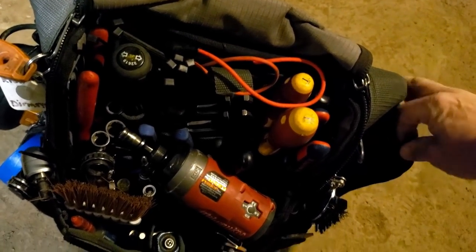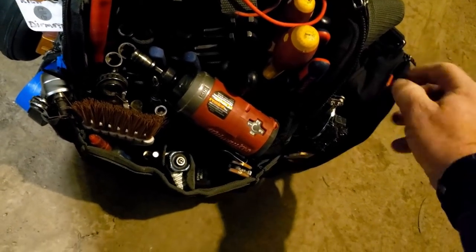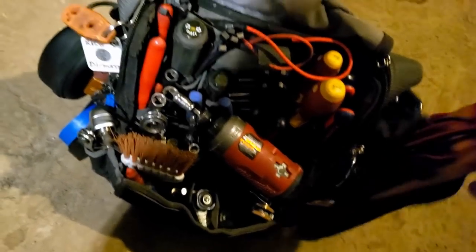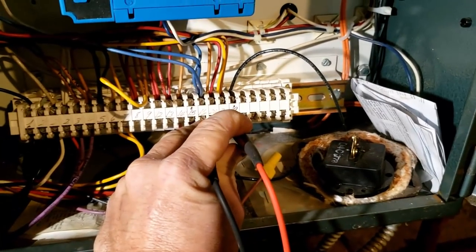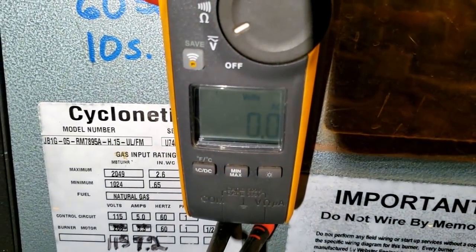I'm going to go ahead and check voltages here on these terminals, but none of that was very well labeled originally. So let's see if we can catch it. This is just one of those things where, you know, it's a major pain in the butt when things don't want to act up the whole time you're there. Alright, 24 and 25 is my damper switch and it shows to be dead.